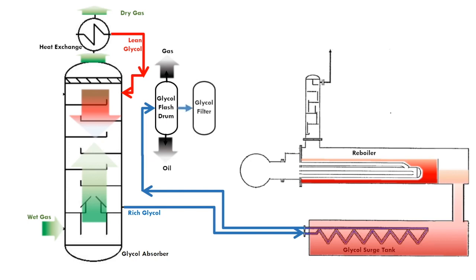The rich glycol then flows into the glycol filter. The purpose is to remove any solid contaminants. Typically, sock type filter will be used. The filter element will be changed periodically, depending on the differential pressure across the filter.